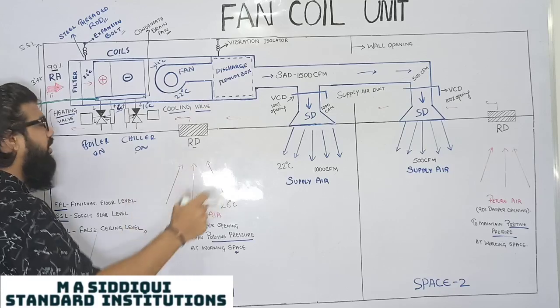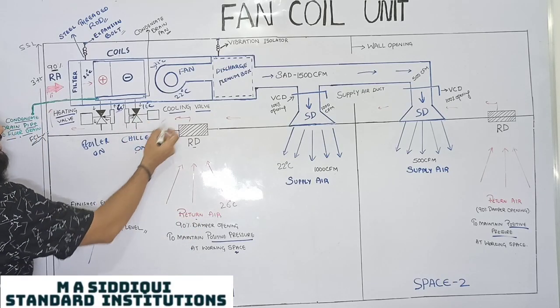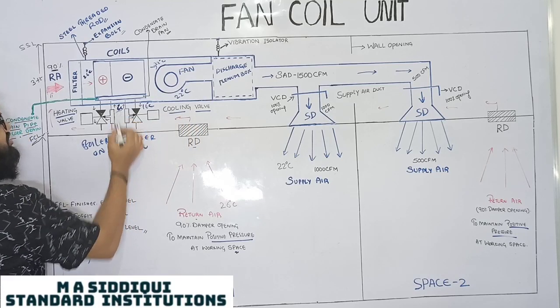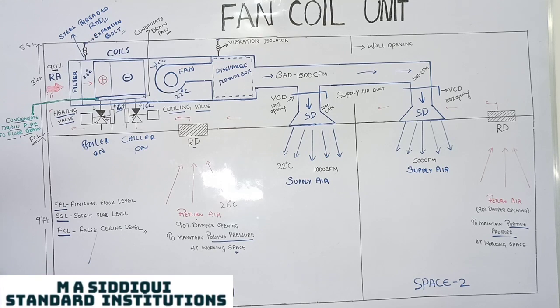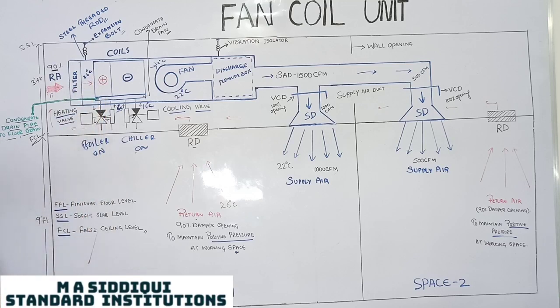So this filtered return air of 26 degrees Celsius has to be cooled or heated. If we want to cool, definitely this valve assembly will get open. That means the cooling valve gets open and from the chiller, we will be getting 6 degree chilled water. If we want to heat this space, the chiller will be off and the boiler section gets on and the high temperature water will enter into the coil.